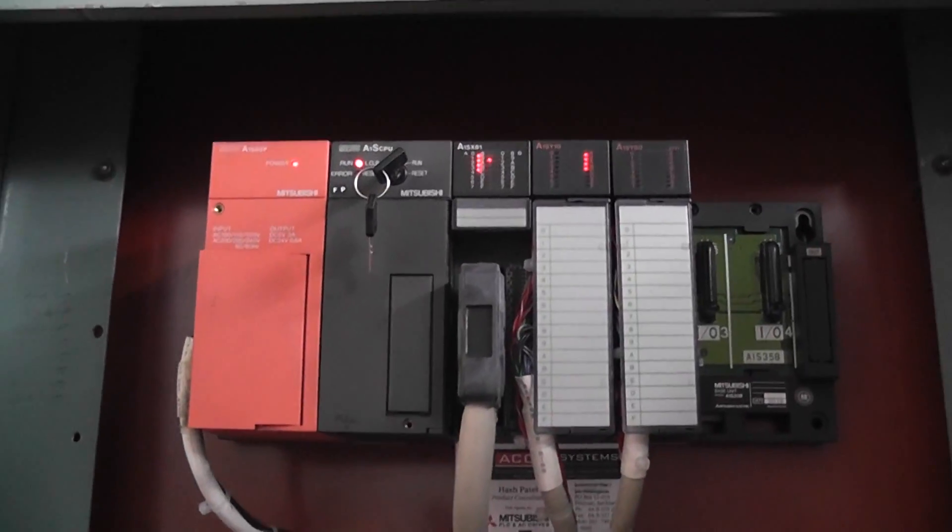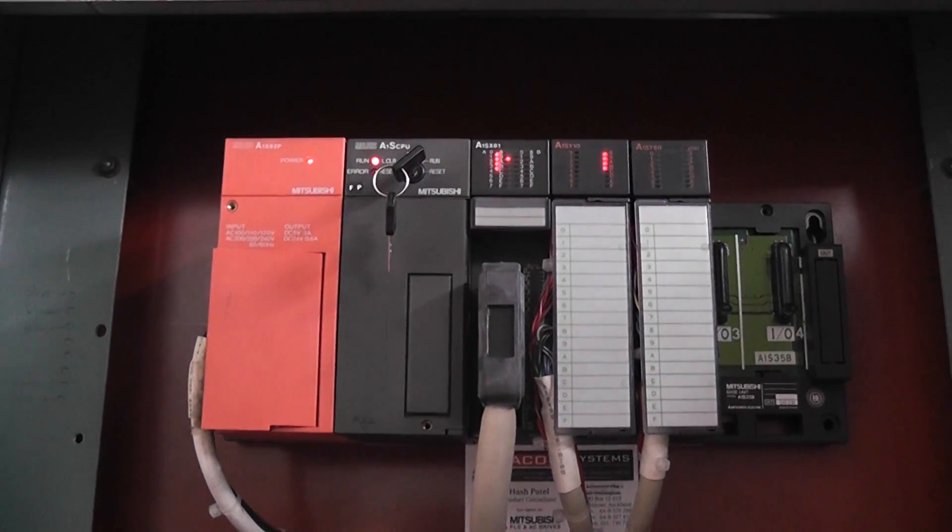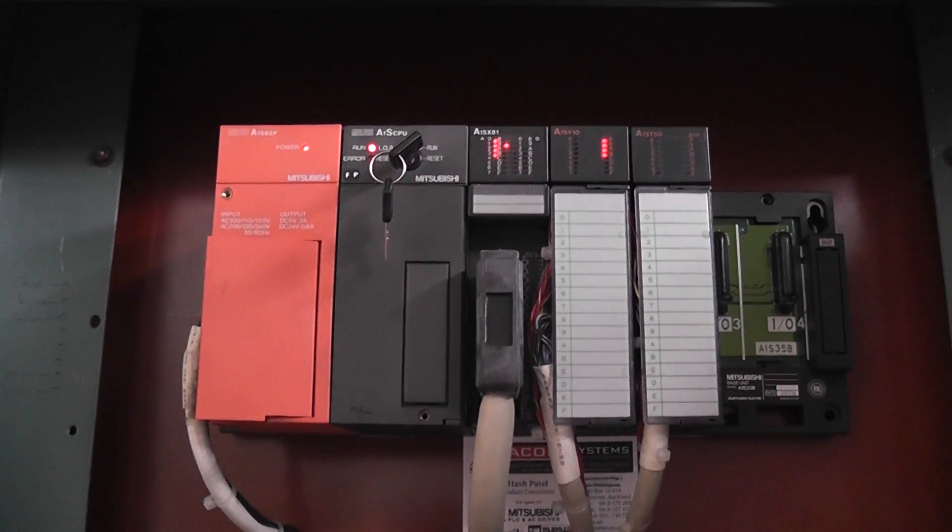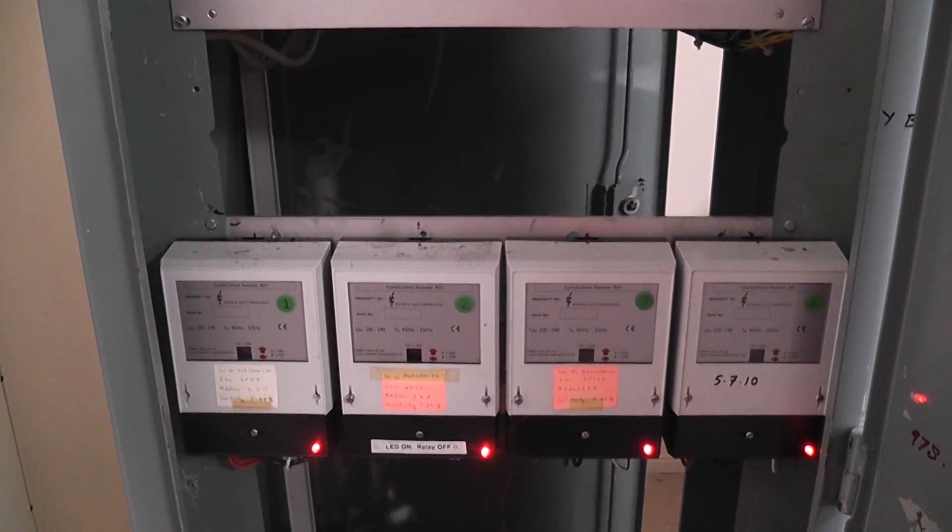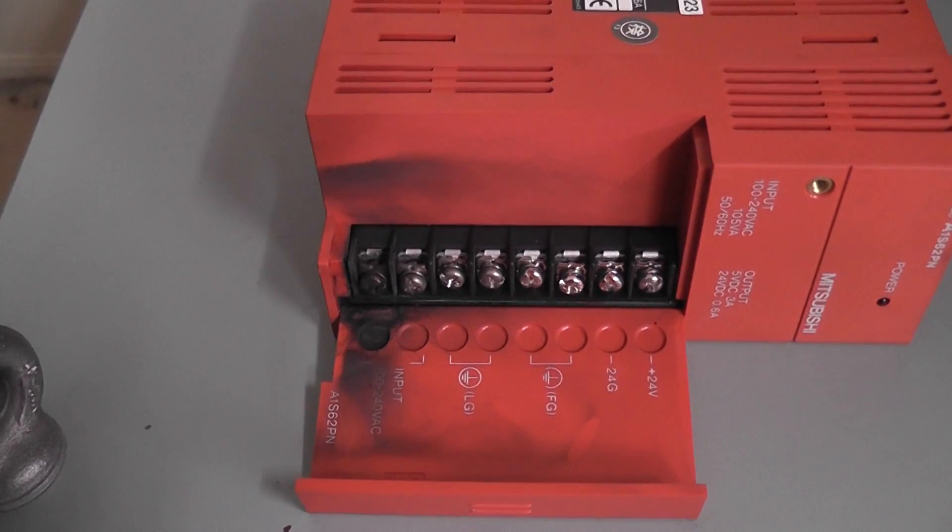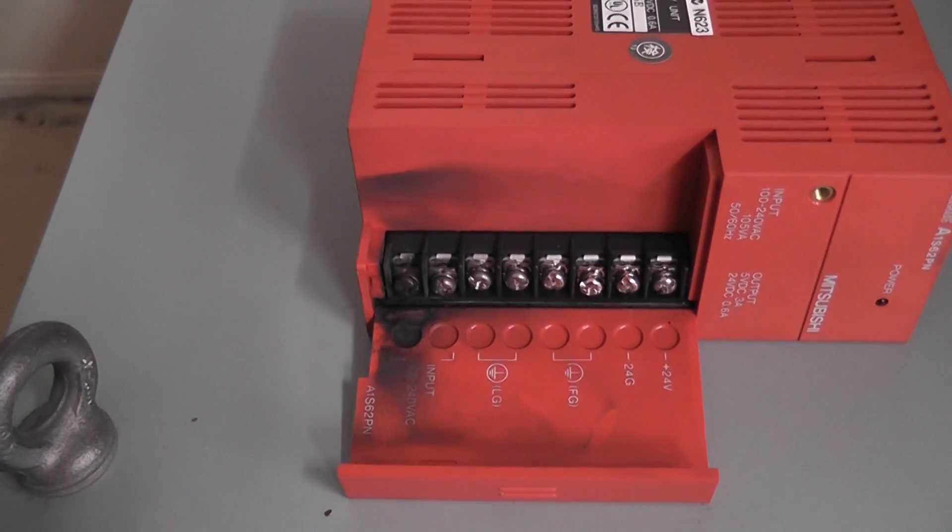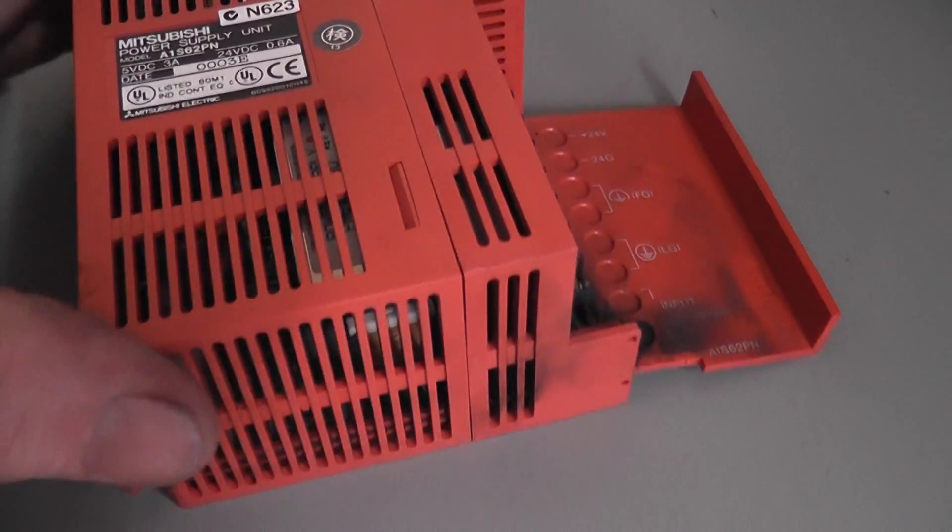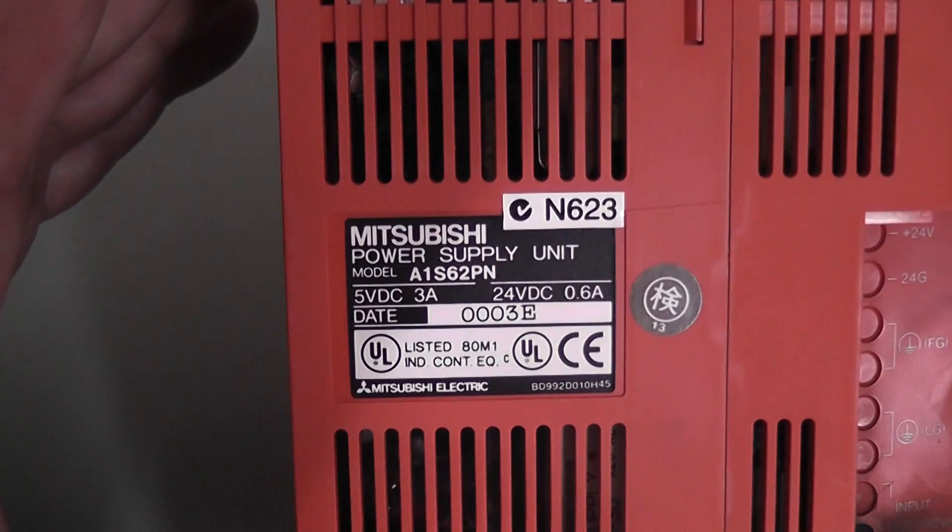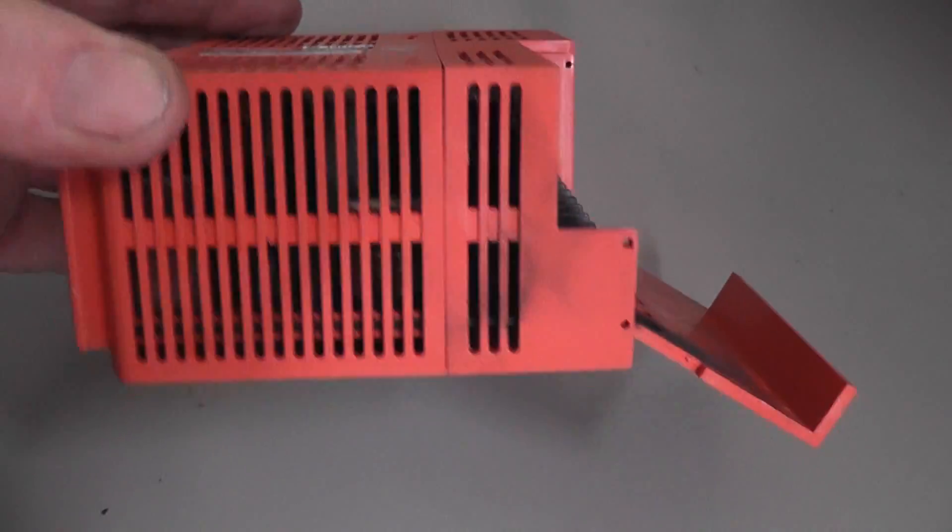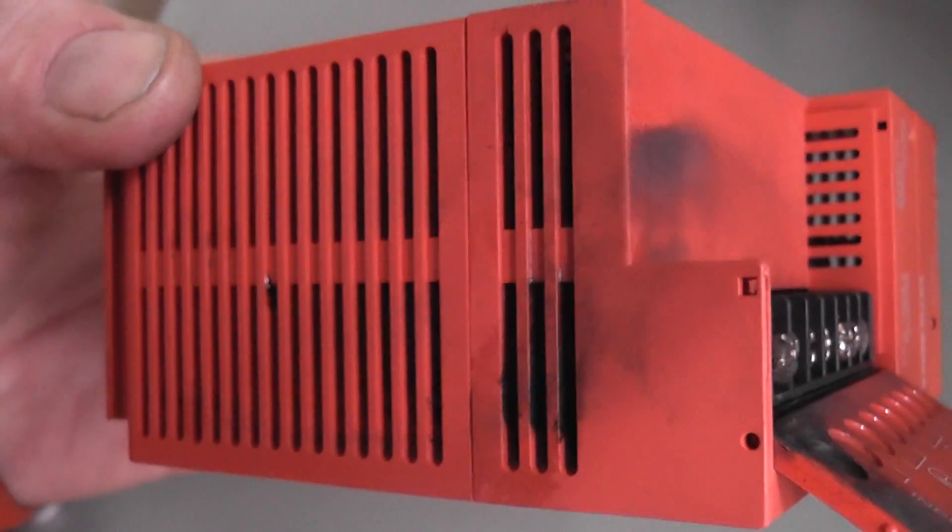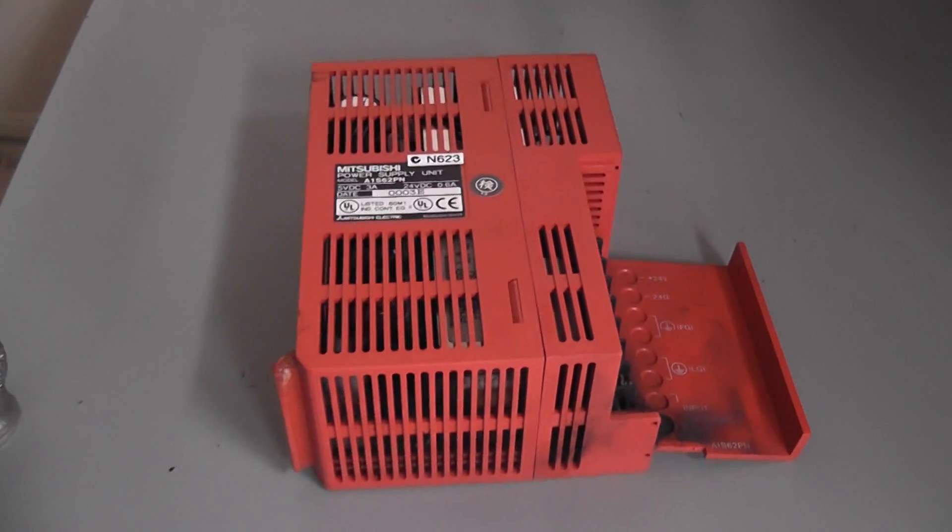That's the PLC that controls it. Hope this video makes sense because I need to remember myself as well. I'm waiting for the transmission to start. That's the blown power supply PLC from Mitsubishi, now about 600 bucks. I need to try to source another one. These components are getting harder and harder to get as the thing is probably about 10 years old.